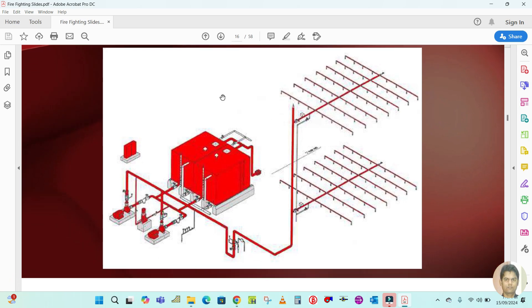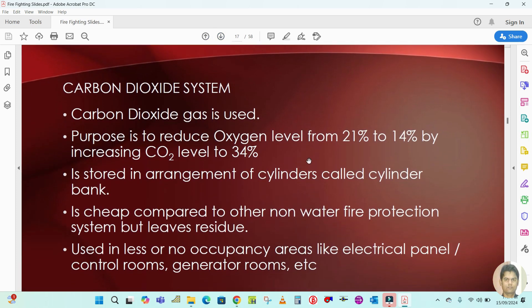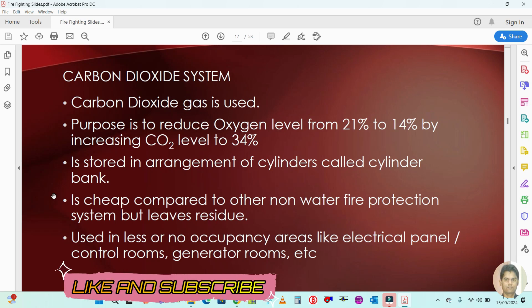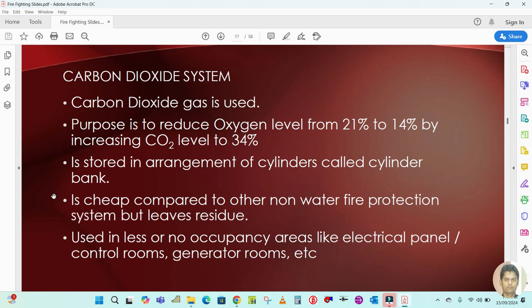Here is the CO2 system. Carbon dioxide gas is used in the CO2 system. The purpose of the CO2 system is to reduce the oxygen level from 21 percent to 14 percent by increasing the CO2 level to 34 percent. If you reduce the oxygen level and increase the carbon dioxide, you are reducing the oxygen, and if you reduce the oxygen, the fire will be extinguished. So the main purpose of the CO2 system is to reduce the oxygen level — if you remove the oxygen, you are removing the fire.